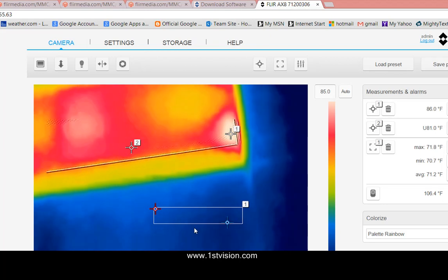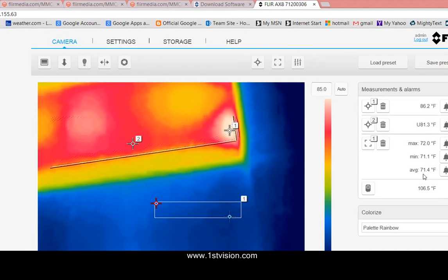And what that shows is the min, max, and average. You can put up the six objects or points that you want to measure and you can remove them by hitting the little trash can. But more importantly what you could do is you could set alarms and this is really how you'd use the camera.